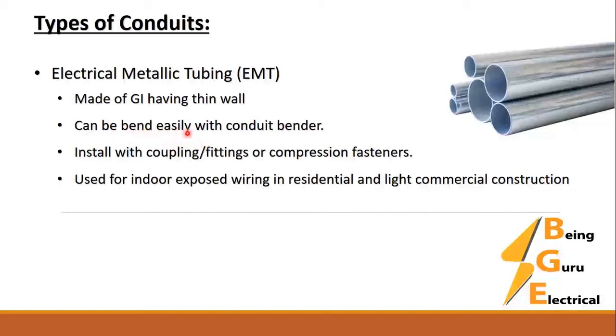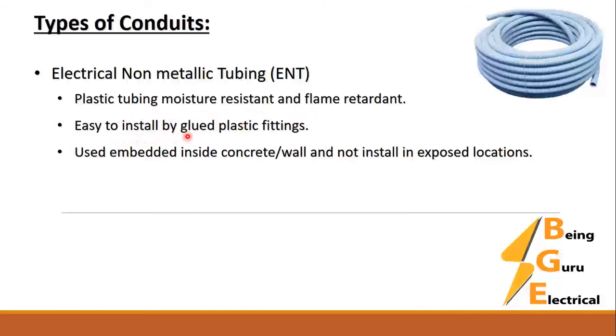Next we have Electrical Non-Metallic Tubing, or ENT. As you can see in the picture, this is a plastic tubing that is moisture-resistant and flame-retardant, and easy to install using glued plastic fittings. It is used embedded inside concrete walls and is not installed in exposed locations — for exposed locations, metallic conduits are used.